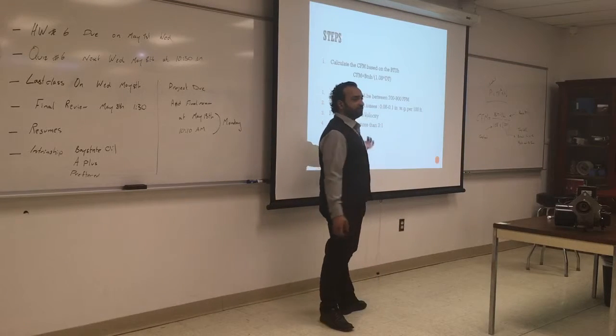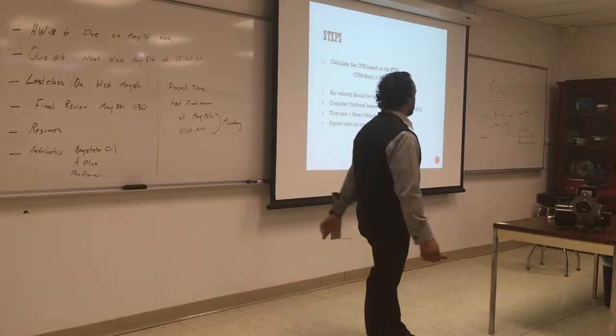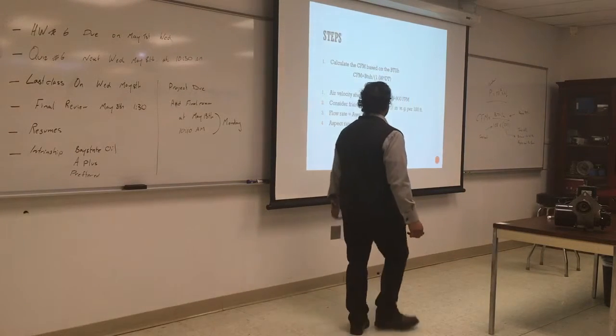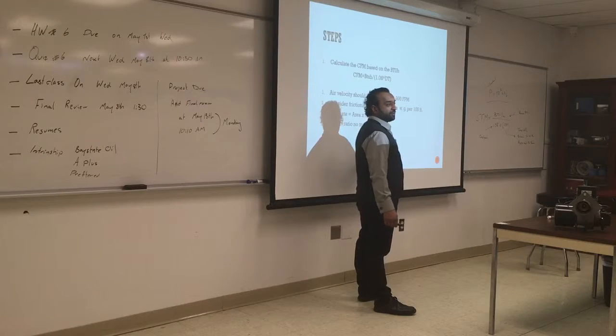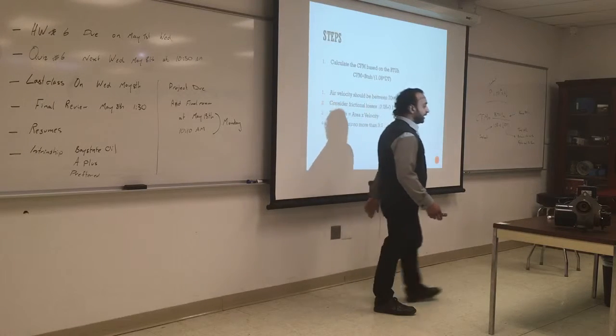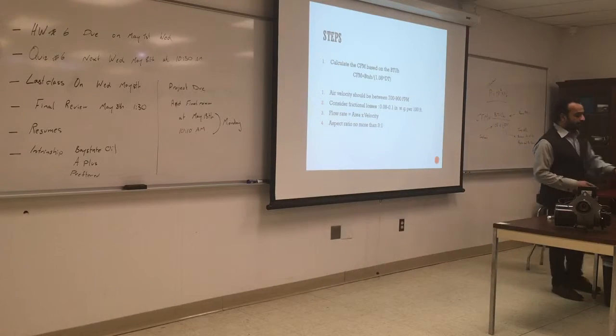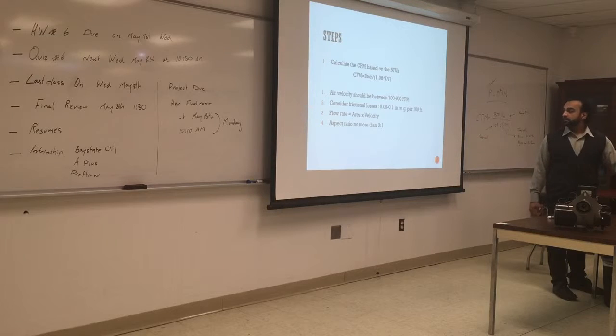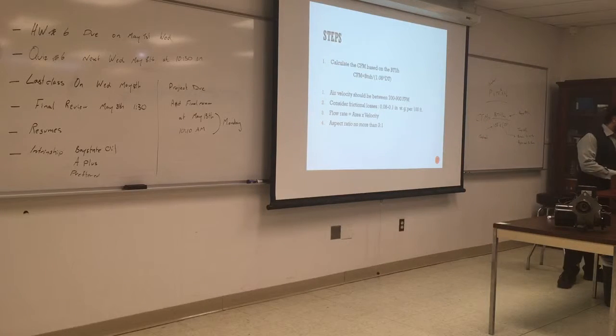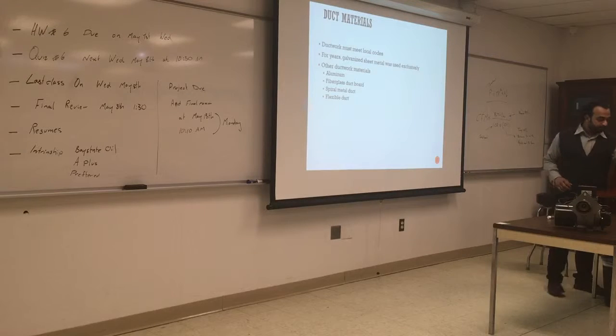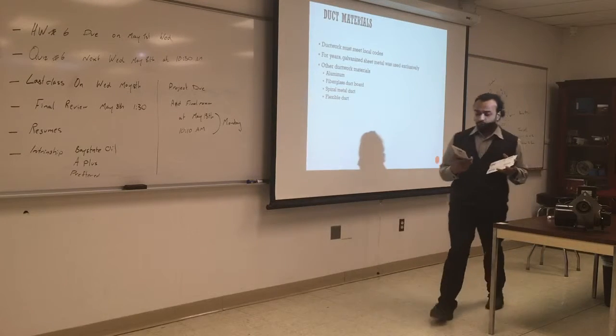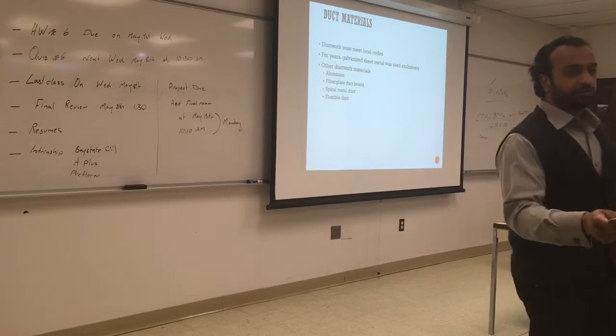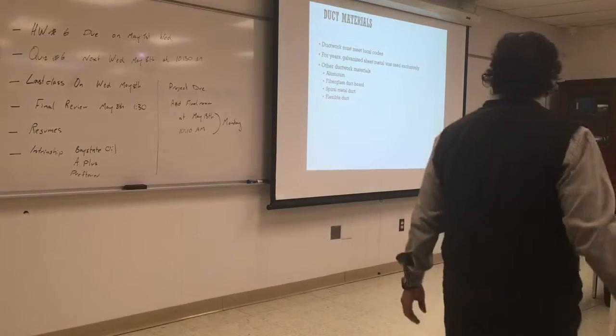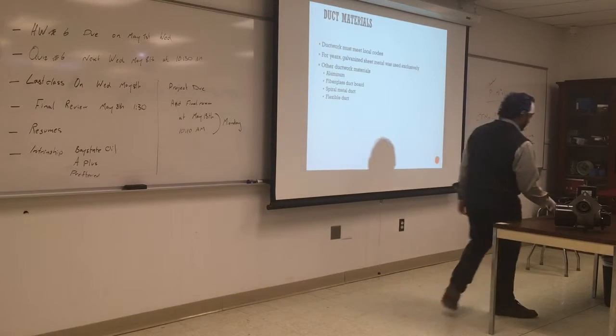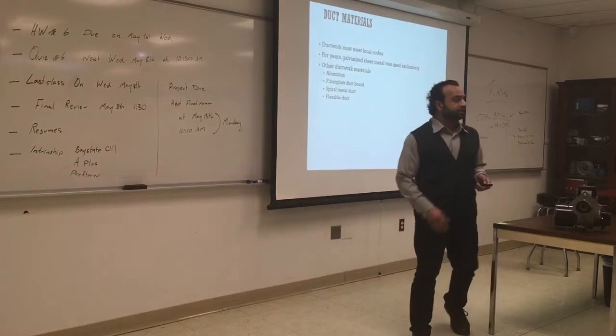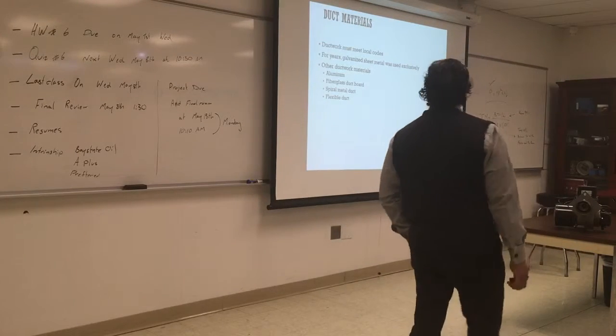And aspect ratio, that's if you are using rectangular duct, you don't want to be more than 3 to 1. So if one leg is 6, the other one should be 2, and so on. For round and square, you go by the total area. I'm going to pass these around so you can look at them and see how they work based on the velocity. They're very easy to use, and you can get some from the supply house. You're not going to go into the math, calculating those will make things a little bit more convenient, unless you have some ugly shaped or really large duct.